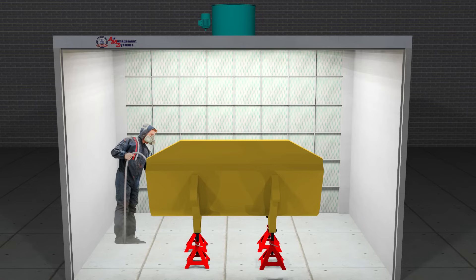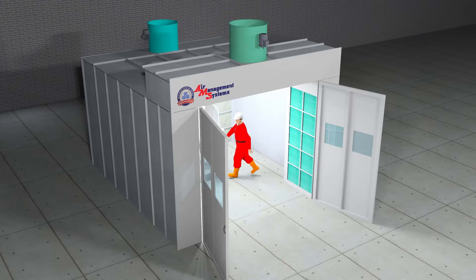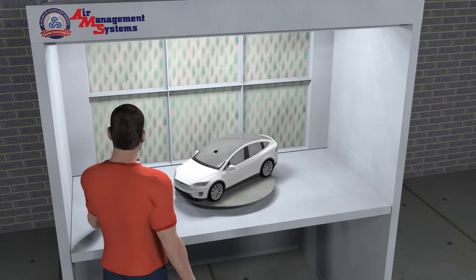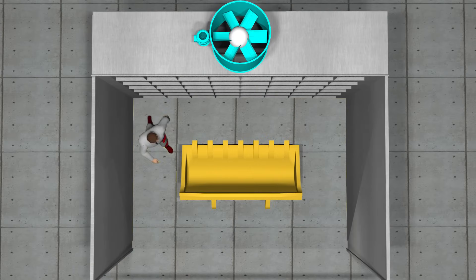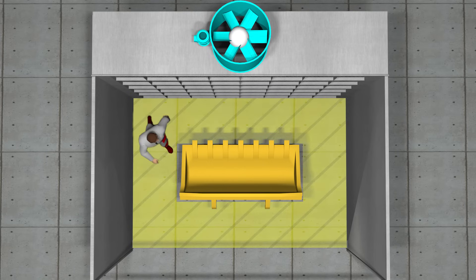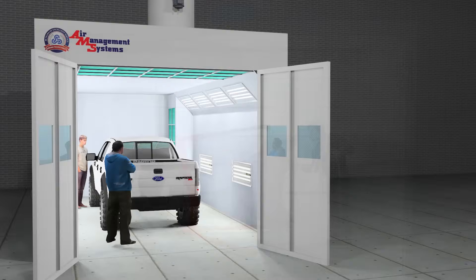For spray paint operations that are more contamination sensitive, a filtered door spray booth or an enclosed spray booth with pressurized or heated air make-up is the right option. Like the bench booth, you will need to either rotate the part or be able to walk around the part to paint it. Plan to have at least three feet all around the product and above it to be able to spray it and inspect it. These spray booths come in every size to fit your needs.